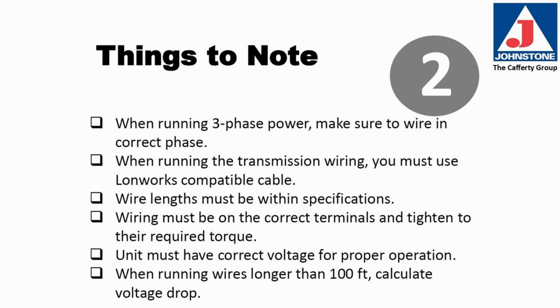Here are a few things to note. When you're running 3-phase power, be sure to get the wiring in the correct phase. When running the transmission wire, you must use Lonworks compatible cable. Wire lengths must be within specifications. Wiring must be on the correct terminals and tightened to the required torque specs. Unit must have correct voltage for proper operation. When running wires longer than 100 feet, calculate the voltage drop.